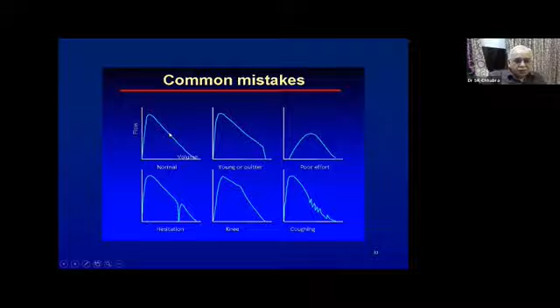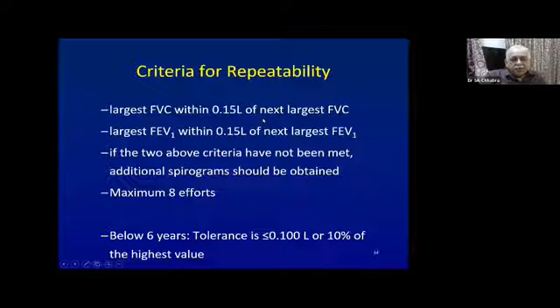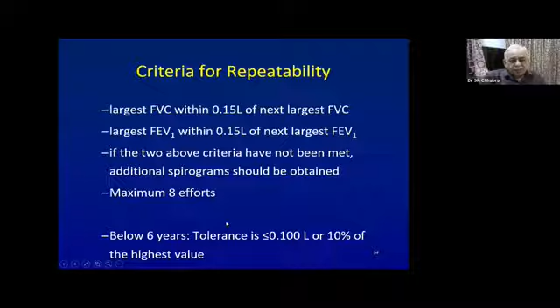Having obtained 3 acceptable curves with this kind of appearance, we then have to see whether the patient's efforts are reproducible. That means the patient's efforts should not differ. The next largest FVC and FEV1 should not be different by more than 150 ml. So we go on doing the test a maximum of 8 times till we get 2 curves where the FVC and the FEV1 are not different by more than 150 ml. For pediatrics, the limit is 100 ml.